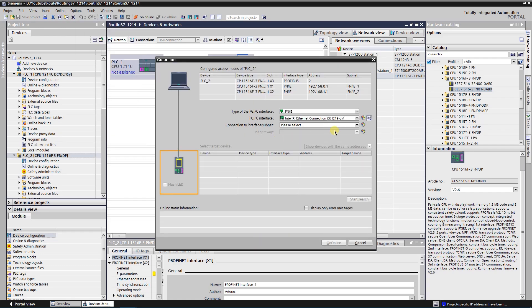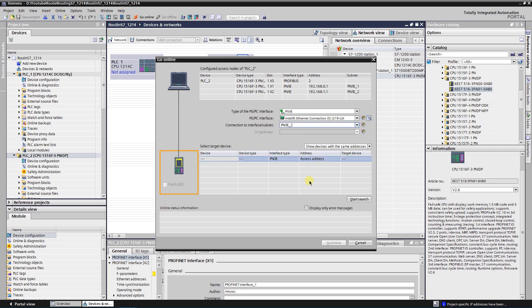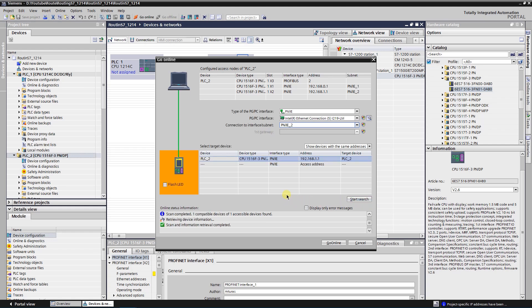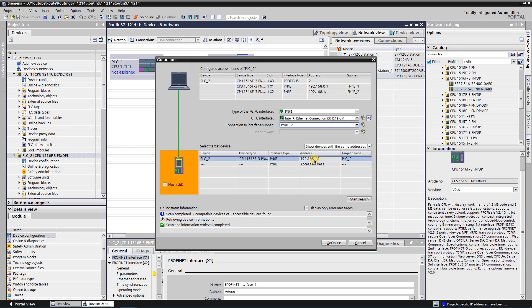Select the interface where your PG/PC is connected to the CPU and then click on Start Search. You should find one. If not, then possible reasons are: wrong subnet selected, wrong IP of your PC, broken Ethernet cable, CPU is not powered, and so on.